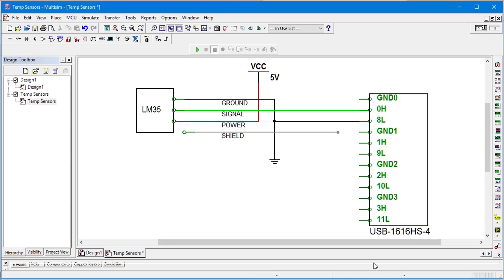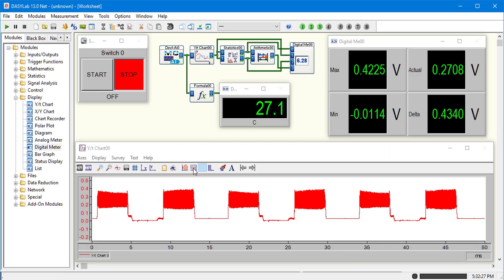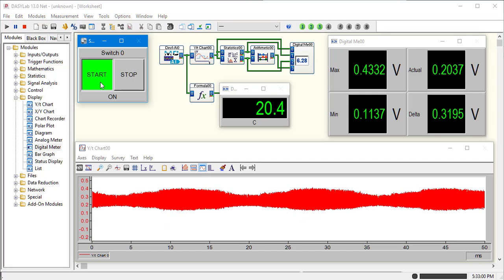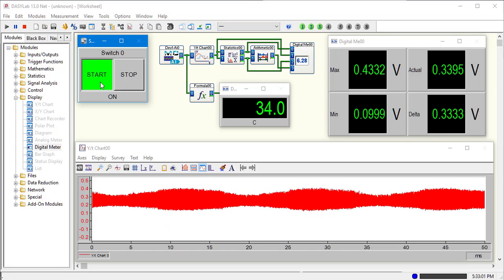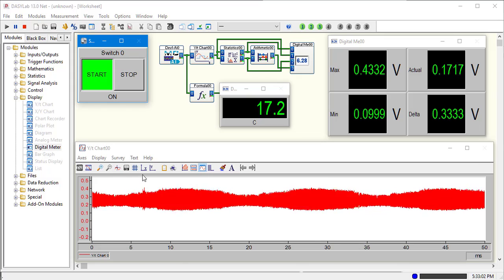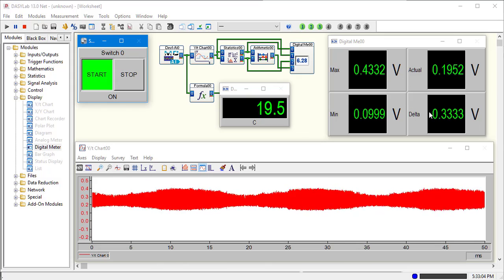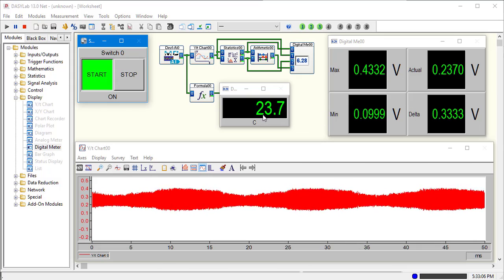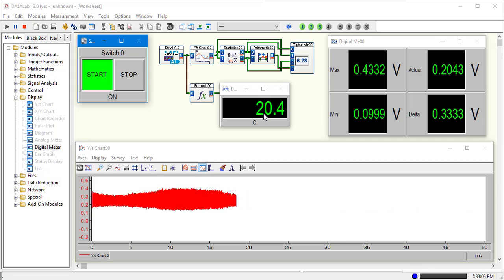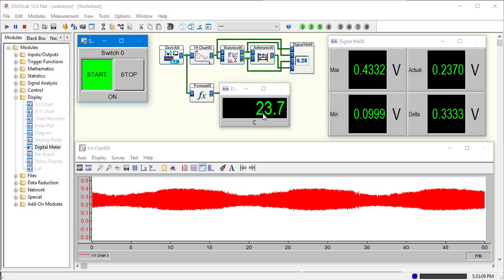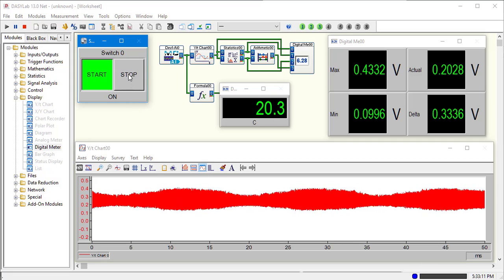If we go back and connect that, our output will be much different. Now that's with the shield connected. We still have quite a bit of noise in this line. As you can see, we're just all over the place trying to get a temperature reading.